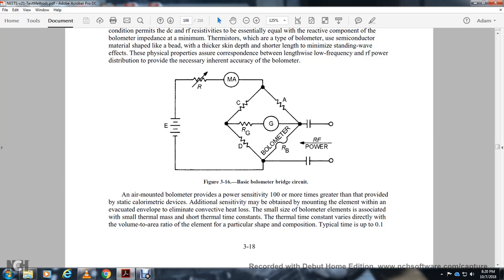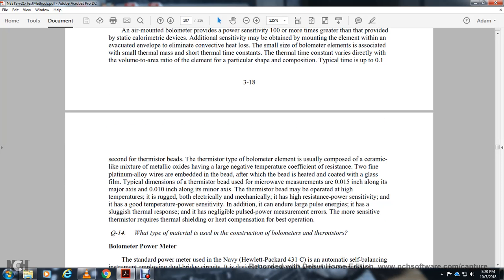The thermistor type bolometer element is made of a ceramic-like mixture of metallic oxides with a large negative temperature coefficient of resistance. Fine alloy wires are attached to the bead. Typical thermistor dimensions for microwave measurement are 15 mils along the major axis and 0.010 inch along the minor axis. The thermistor is highly resistant both electrically and mechanically. Power sensitivity is good across temperature, and the thermistor is capable of handling large pulses of energy. The thermistor resistor provides the best operation with thermal compensation.